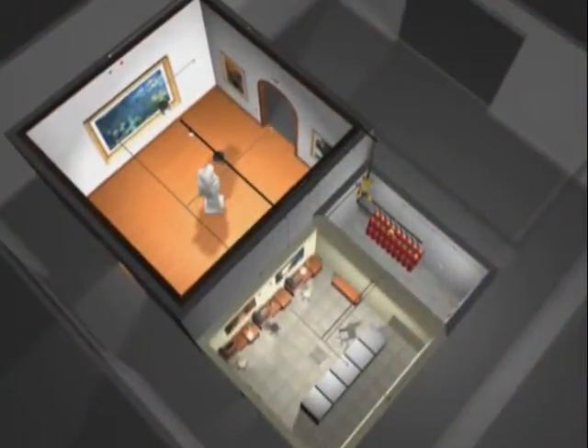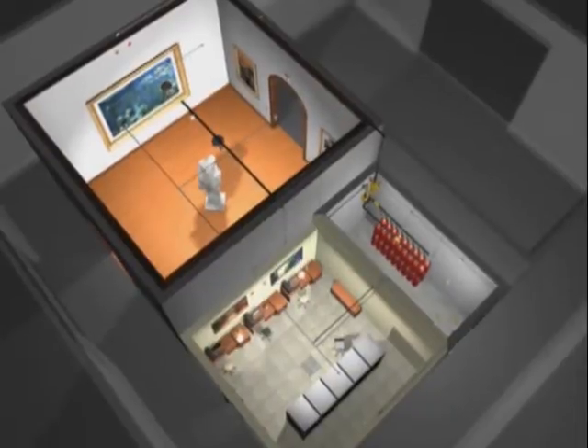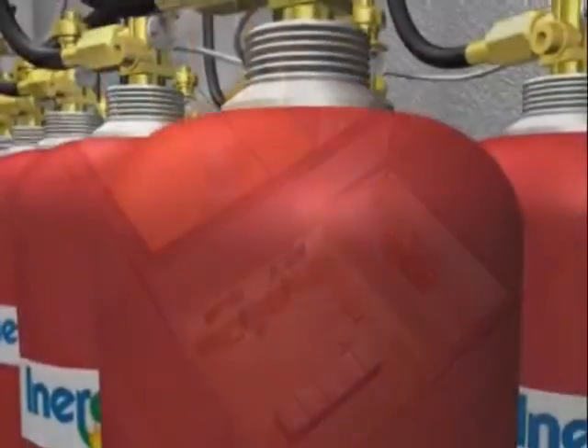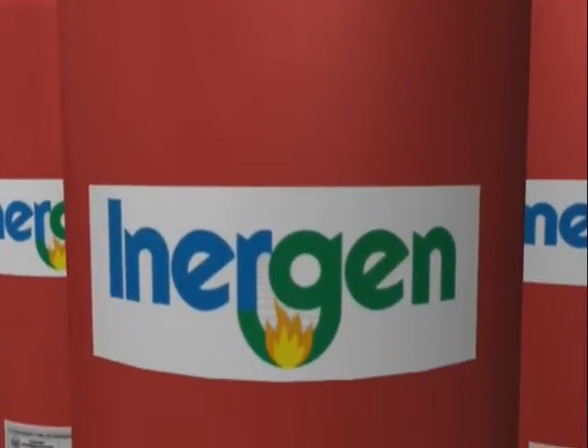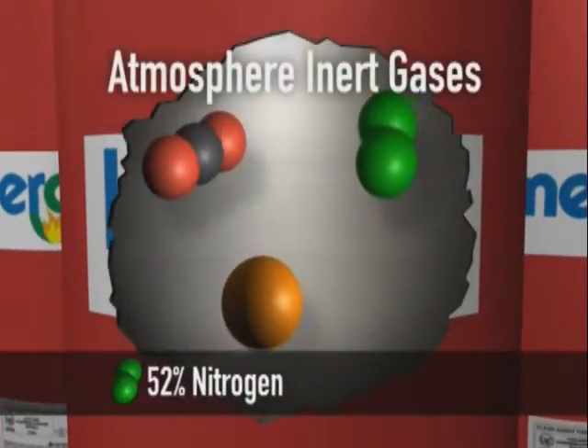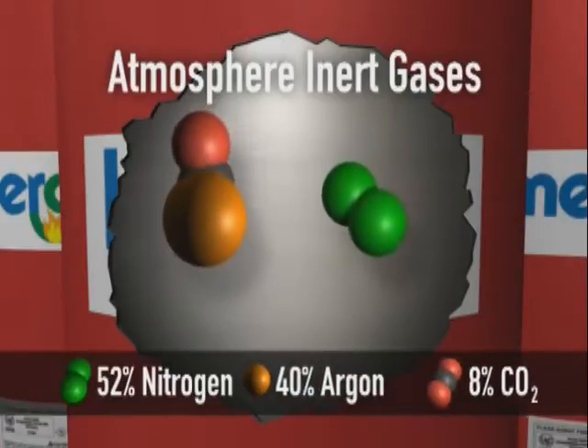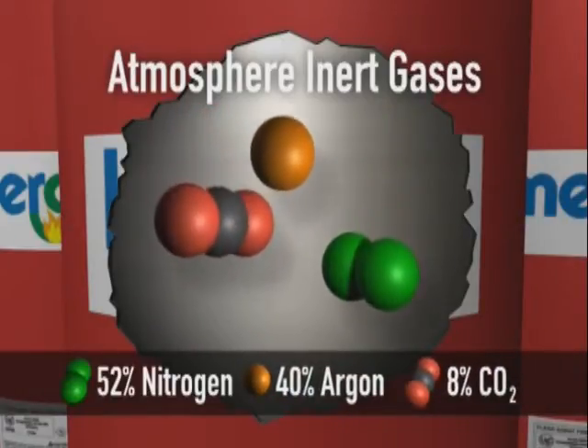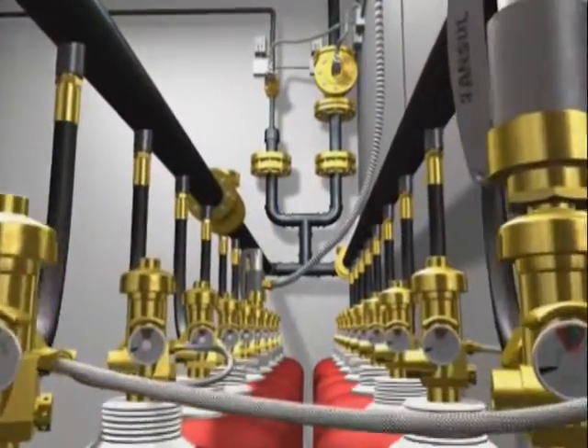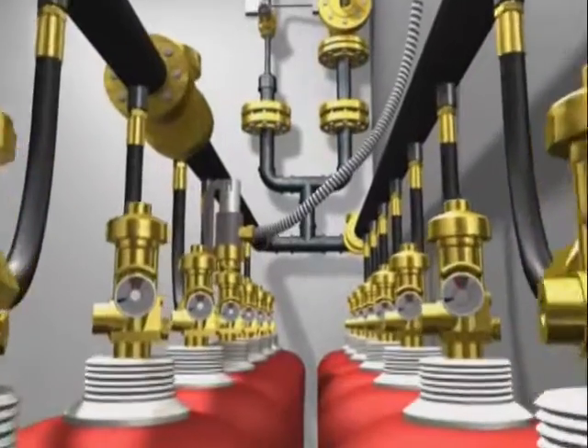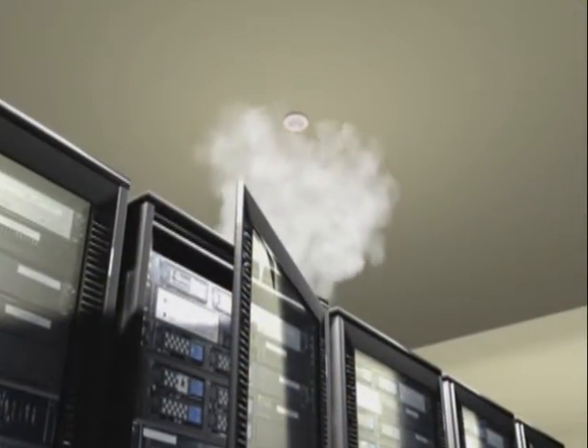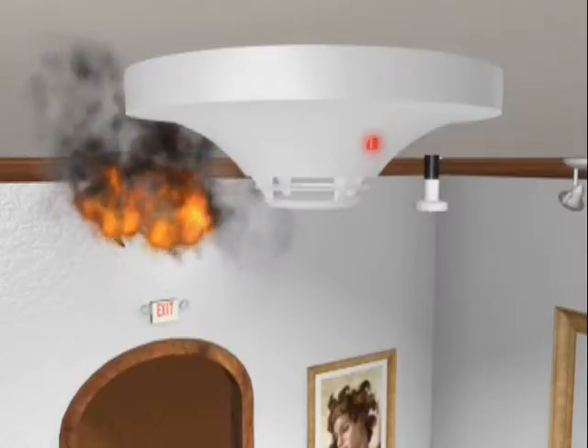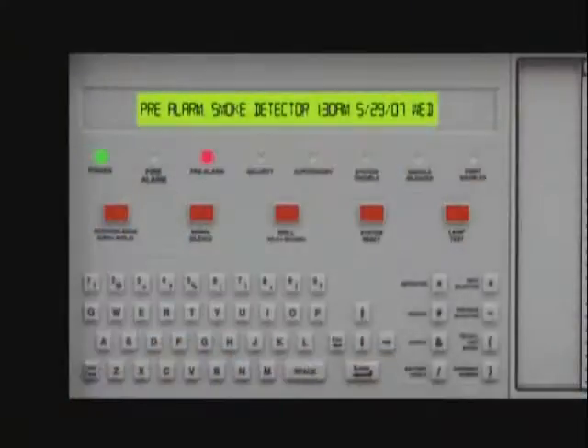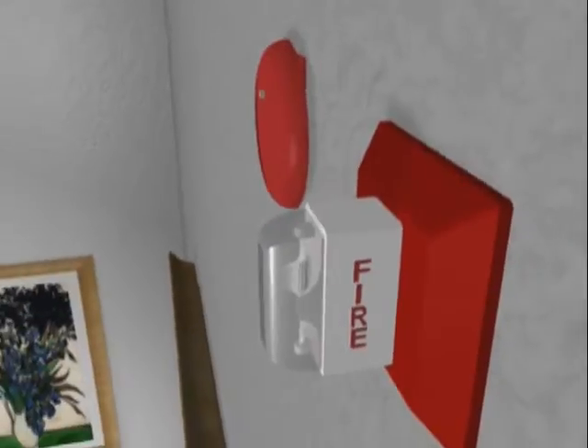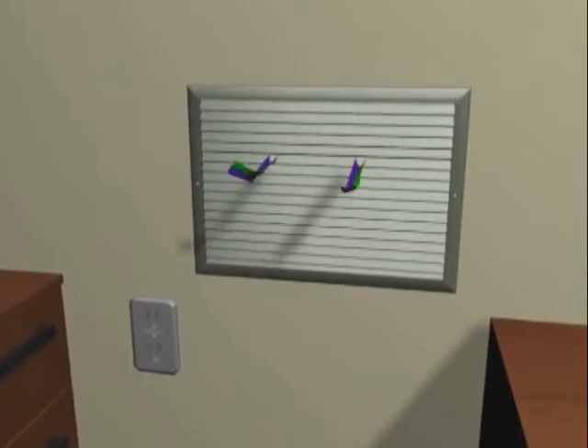An Inergen clean agent fire suppression system is both innovative and flexible in design. Inergen is a combination of three naturally occurring inert gases from the Earth's atmosphere. It is comprised of 52% nitrogen, 40% argon, and 8% carbon dioxide, common components of the air we breathe. Inergen is stored in a series of steel cylinders located outside of the protected areas. When smoke, heat, or particulates are detected, an electronic signal is sent to the autopulse control unit, triggering a series of critical actions. Audio and visual alarms are started. The ventilation systems are closed off.